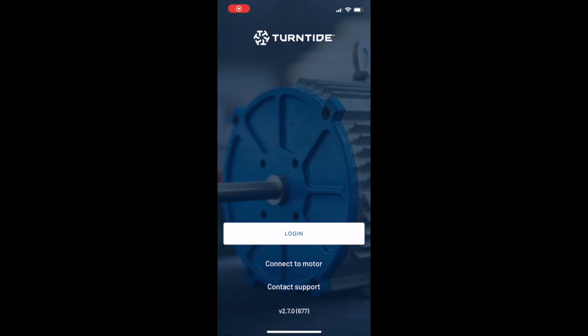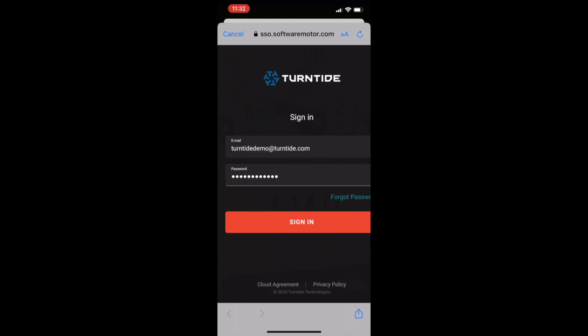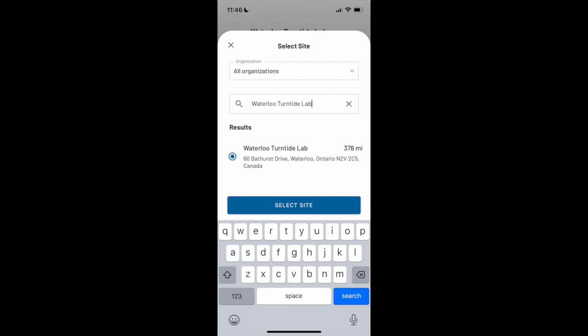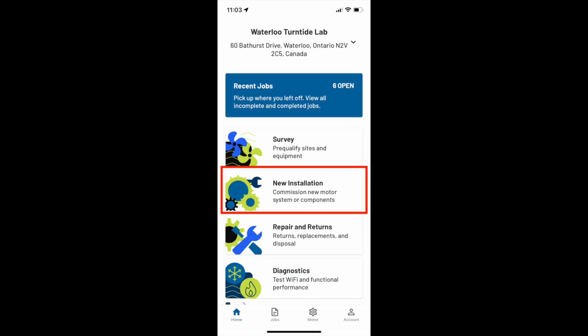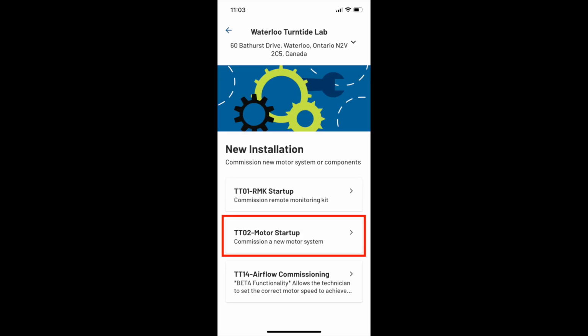Next, log in with your email and password. Once logged in, you will need to select the site where the install is taking place. Note that the nearest sites to your physical location will be listed at the top. If you do not see this site in the app, please call your supervisor or Turntide support. It is good practice to log into the app and verify that the site is present the day before the job. Once you have selected the site, select New Installation and choose TT02 Motor Startup.